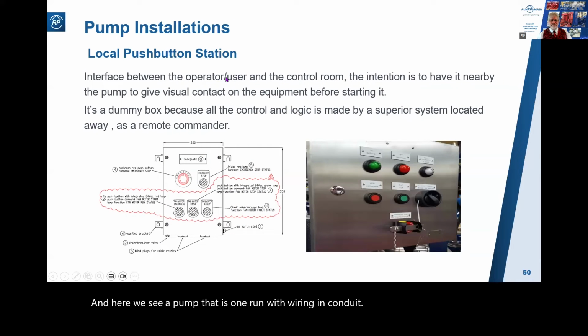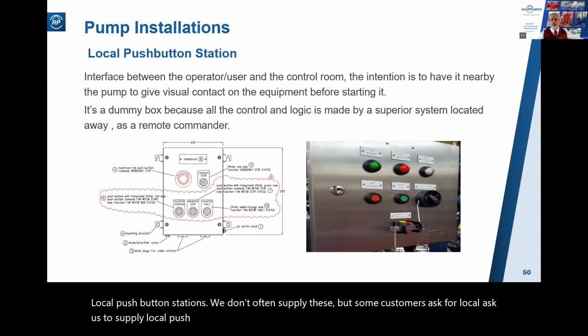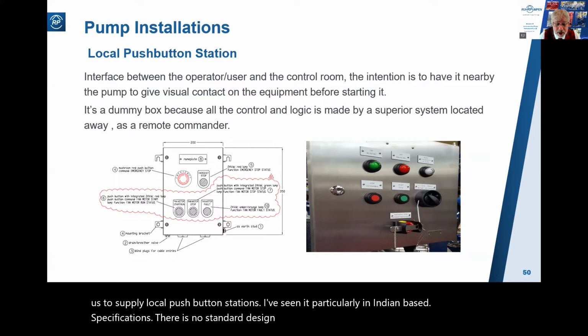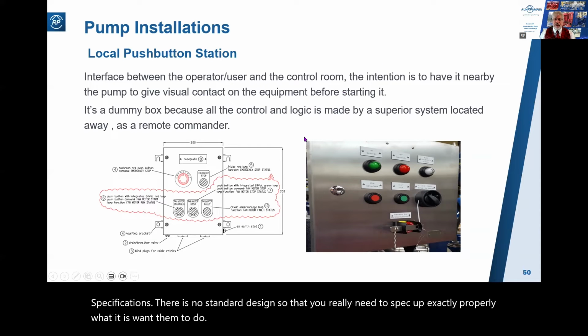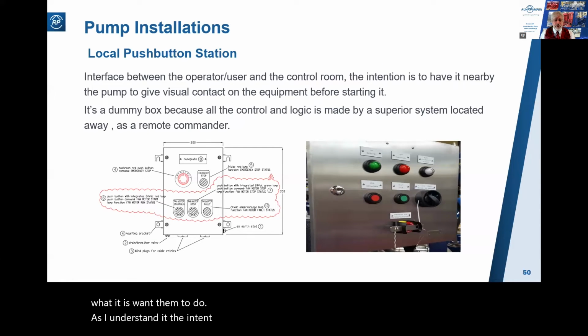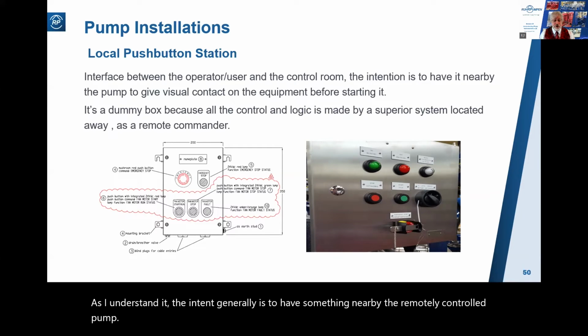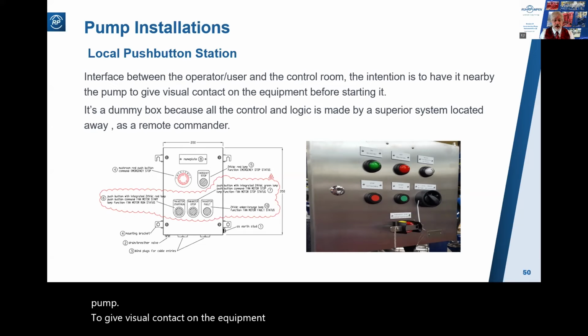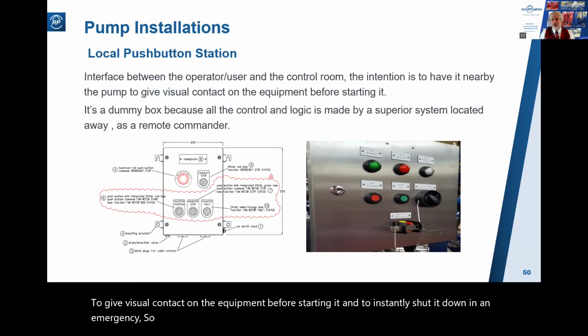Local push button stations. We don't often supply these, but some customers ask us to supply local push button stations. I've seen it particularly in Indian-based specifications. There is no standard design, so you really need to spec up exactly properly what it is you want them to do. As I understand it, the intent generally is to have something nearby the remotely controlled pump to give visual contact on the equipment before starting it and to instantly shut it down in an emergency. So that's what can be supplied if you want it.